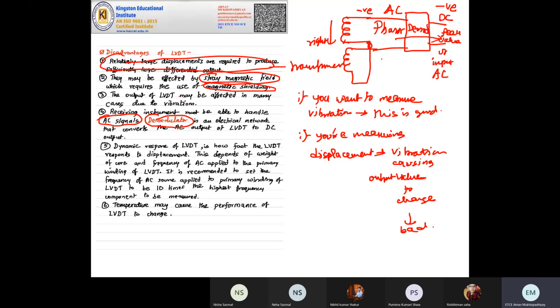Then the dynamic response of LVDT is fast, but limited by the weight of the core and the frequency of the applied AC. If you're moving that LVDT too fast, you won't get an adequate response. Why? Because the arm cannot move that fast - the arm has some weight.